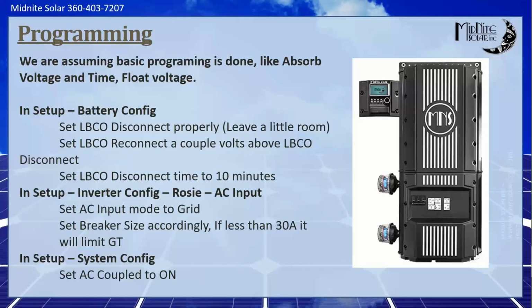But when you first fire up the system, it's going to ask you to give it a name, set all your settings, what type of battery it is, what your programming charge points are, and time and date. And time and date's important. We just worked a tech support call where the customer's system was waking up in float every morning. It took us a few minutes to find it, but they had the time set for AM instead of PM. So the units were thinking that midnight was actually happening at noon, and it was starting a new bulk charge at noon instead of midnight. So that's one that's important to get.